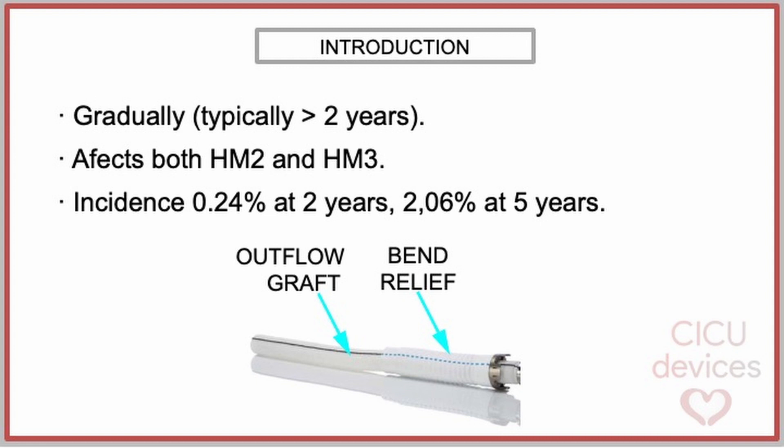The Kaplan-Meier estimate for the incidence rate of extrinsic obstruction post-implantation is 0.24% at 2 years and 2.06% at 5 years.